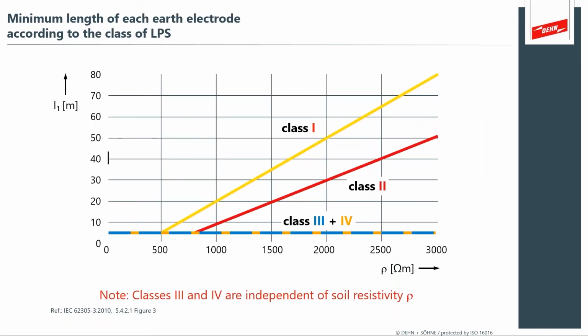So, the minimum length of the earth electrode. This question has come up several times and I'd like to present it again. What we know about the IEC systems is that they dictate class of lightning protection. The more severe class of lightning protection, class 1, requires a deeper electrode and more electrode contact with the soil. So if the soil resistivity is very high, as in dry, stony soils, you need more electrode in contact for the more stringent class 1 lightning protection classification. And this allows the control of risk. Class 1 is the highest class of protection, which controls the risk of lightning damage.